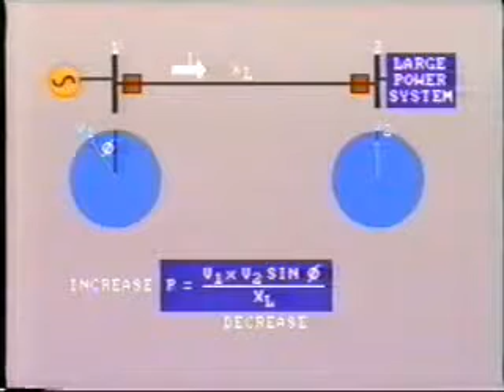But let's look at this other factor again, the power angle phi. This curve shows the transfer capability of the transmission line with relation to the power angle between the voltages at each end. When there is no angular displacement across the line, there will be no power flow. As the power angle increases, so does the load transfer.